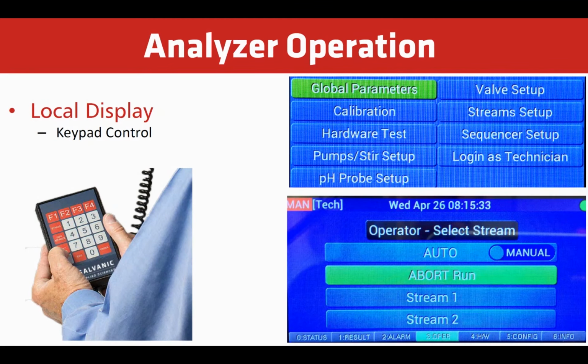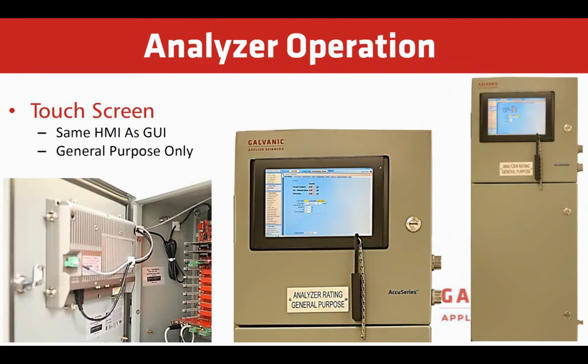And from here, that's where you will perform various setups such as calibration, analog outputs to what you want, or the Modbus settings, all done from a local keypad. We also offer it with a touchscreen HMI panel PC. At the moment, this is for general purpose areas only, not for hazardous area locations. There's a picture of it right there, the touch panel. So that takes the place of the keypad.